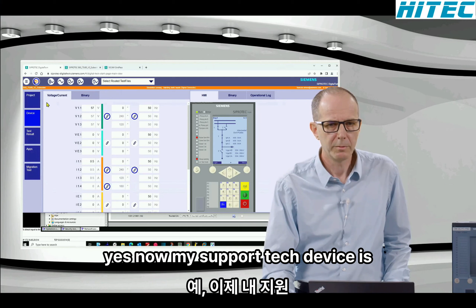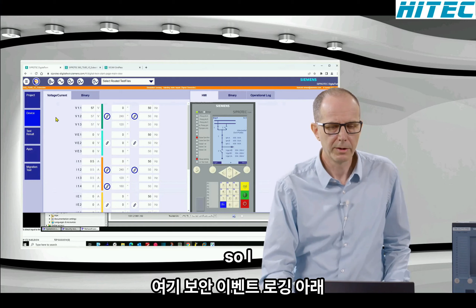Yes, now my SIPROTEC device is running as a digital twin. So I see that I have configured, here under DIGSI, in security event logging, the IP address of my Visual Syslog server and the port - that's only what I have to do. And if I want, I can also send it to a redundant server.